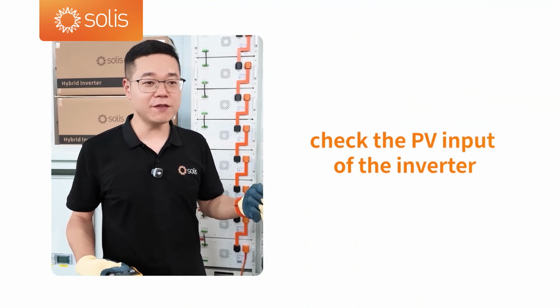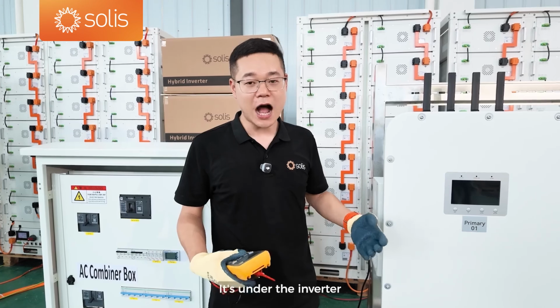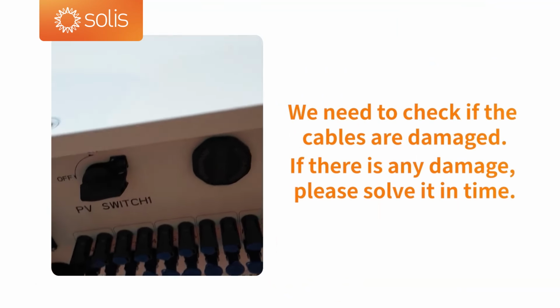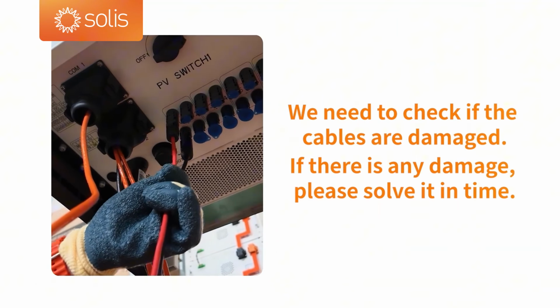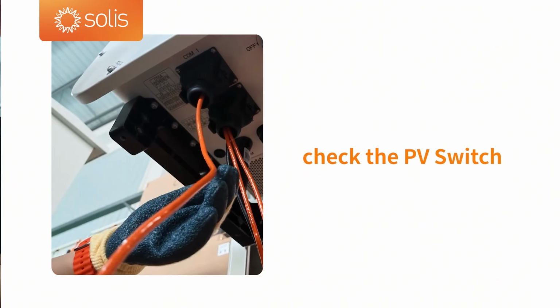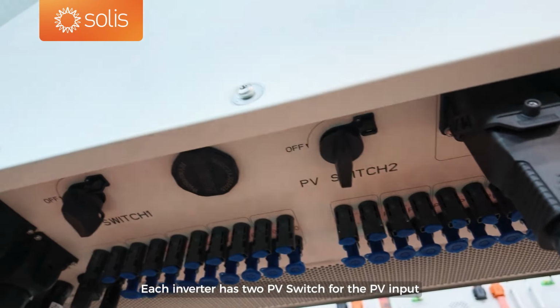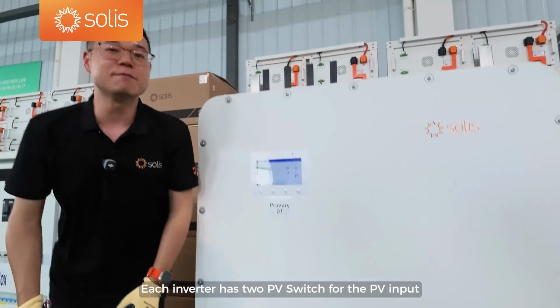First, check the PV string input of the inverter. It's under the inverter. We must check all the PV string connections. After this, we check the breaker of the PV input. Each inverter has 2 breakers for the PV input.